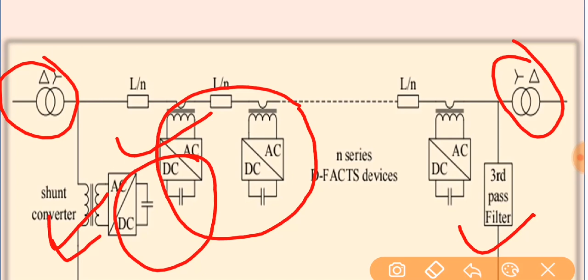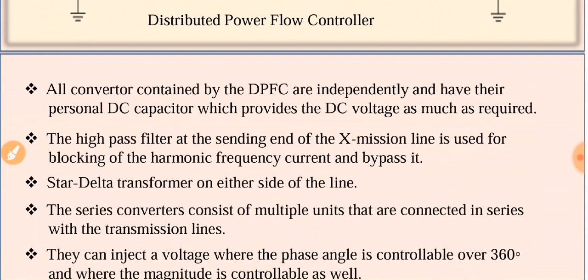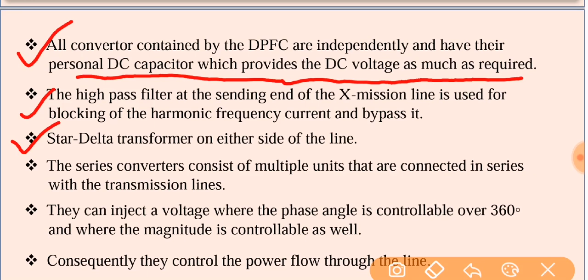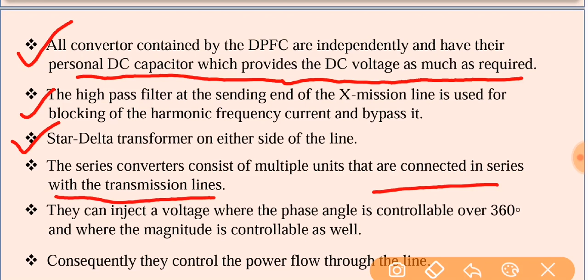Now we see the theoretical part of the DPFC. First of all, all converters contained by DPFC are independent and have their own DC capacitor, which provides the DC voltage as required. Second, a high pass filter at the sending end of the transmission line is used for blocking the harmonic frequency current and bypassing it. Star delta transformers are on either side of the line. The series converter consists of multiple units that are connected in series with the transmission line, which is shown in the above diagram.